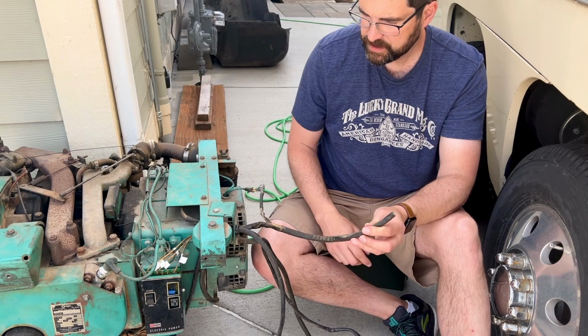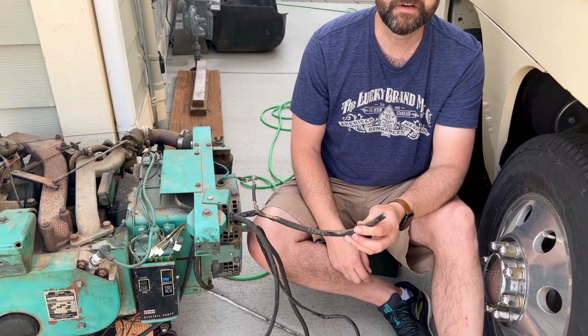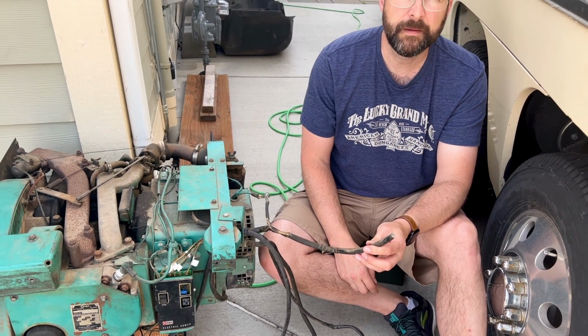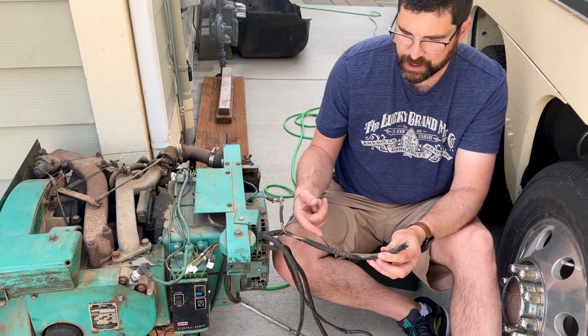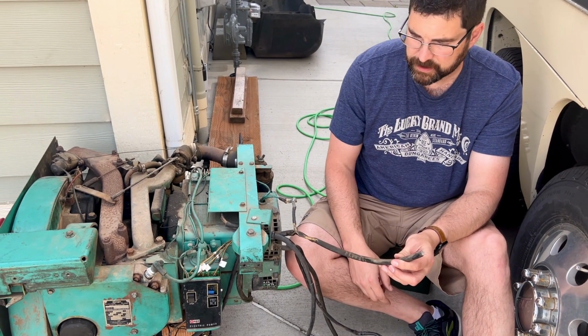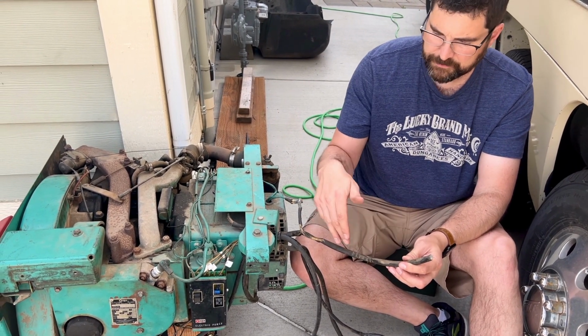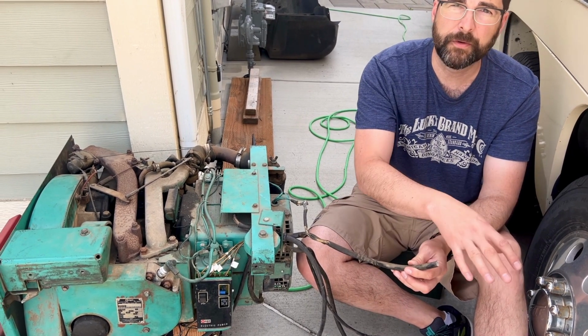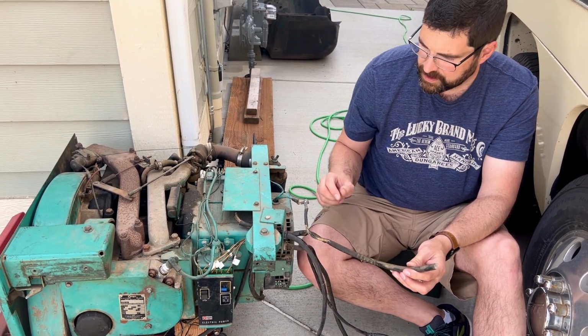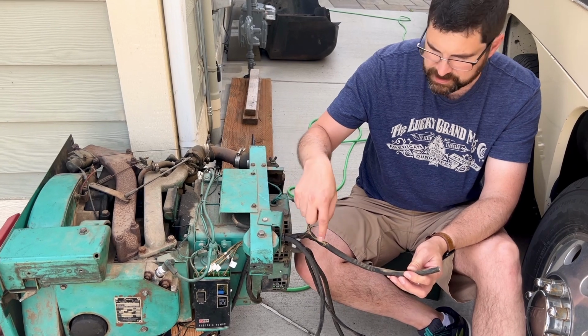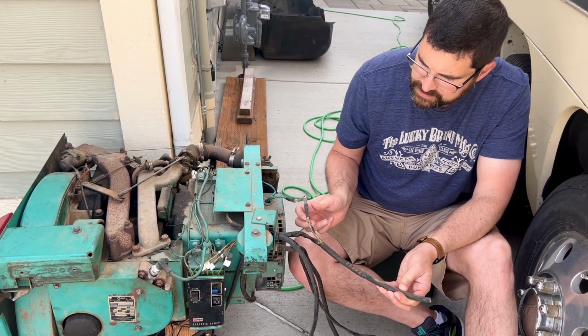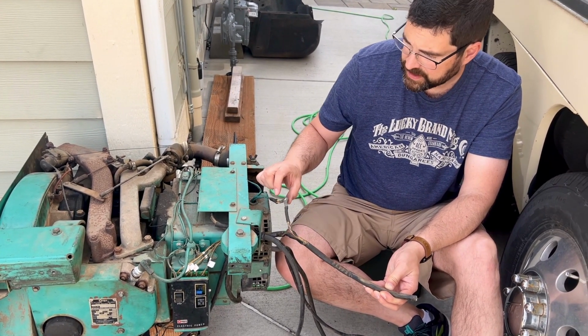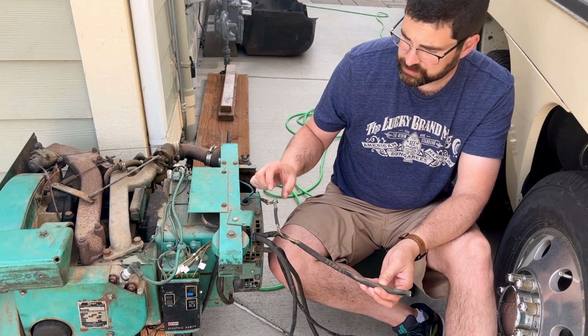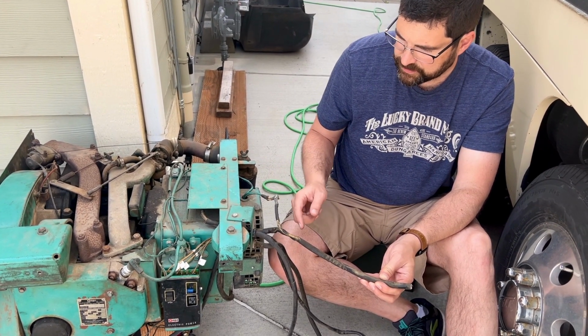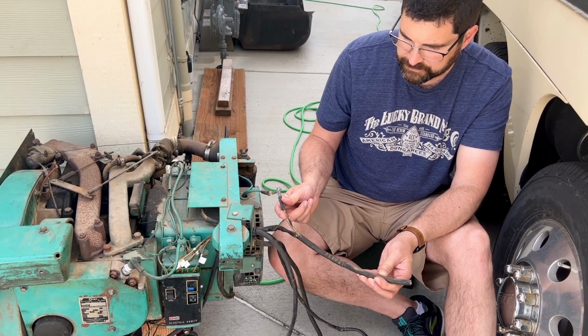This was cut off when the generator was removed from whatever coach it came out of before, and this is the output for the generator. It needs to go, with the metal conduit here, to the electrical box inside of the cabinet, but I need to do something about what's going on here, it's kind of frayed. I don't know what's going on with this nut and bolt thing, so I think I'm probably just going to replace all of this wiring.